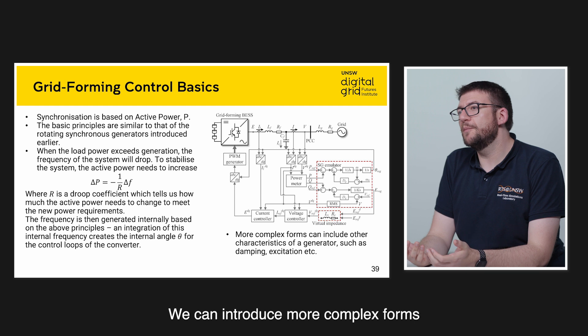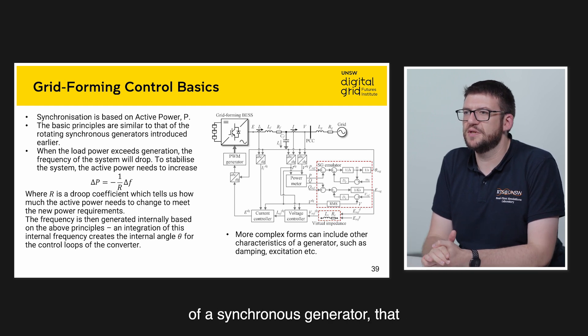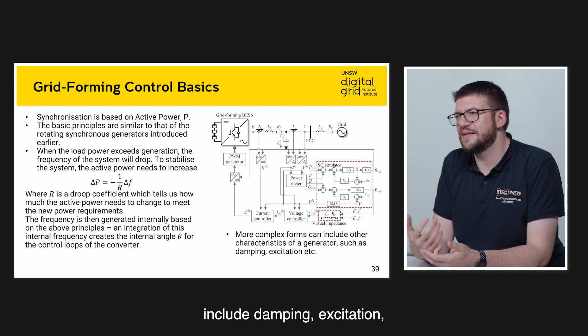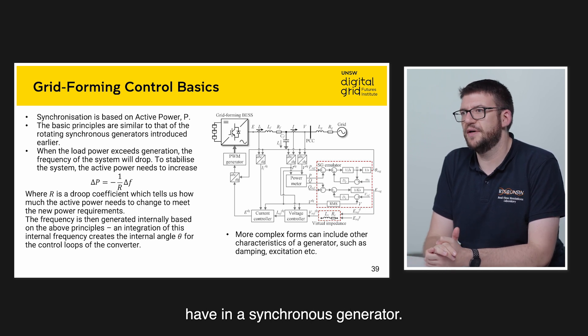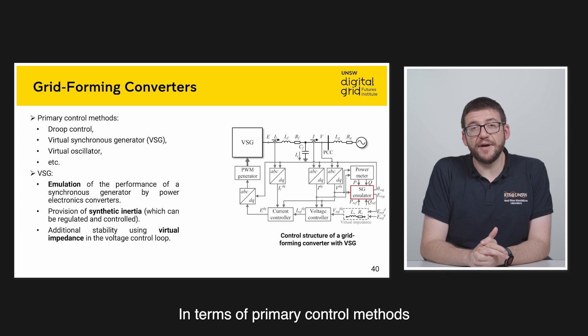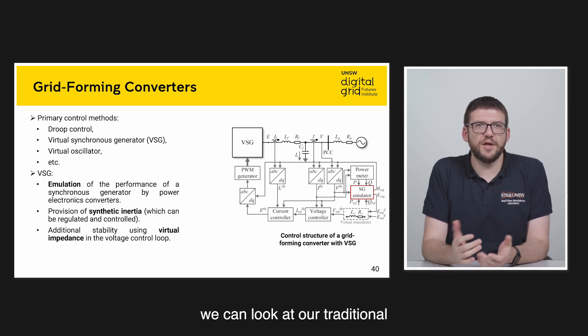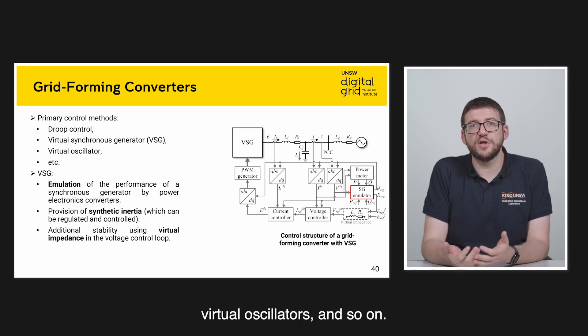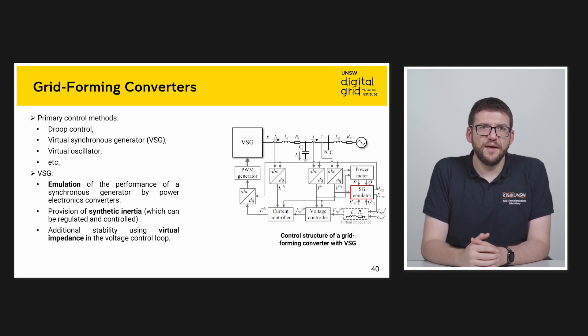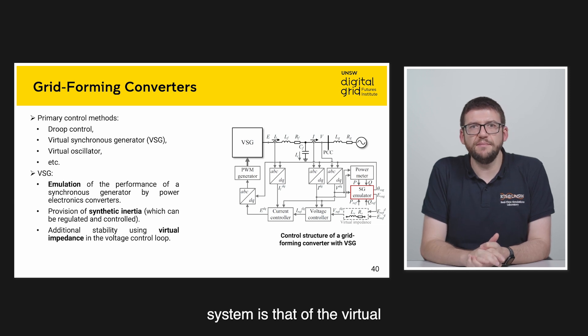We can introduce more complex forms of grid-forming converters that are able to emulate the characteristics of a synchronous generator, including damping, excitation, or any other controller that we have in a synchronous generator. In terms of primary control methods introduced in a grid-forming converter, we can look at traditional droop control, but we can also see virtual synchronous generators, virtual oscillators, and so on. The one that we see as more promising in implementation on a power system is that of the virtual synchronous generator, or VSG.